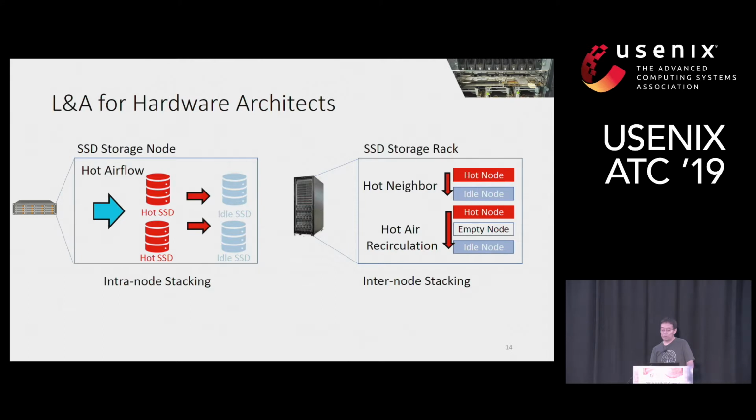In our logs, we have seen SSDs rise above the ambient temperature by up to 25 degrees C or higher. The paper has more details on how, in our experiment, each type of passive heating can heat up an idle SSD under our standard rack setup. The reason this only happens in the one particular data center is that in all the other data centers, a service owns a whole rack. All the nodes in the rack belong to the same service. So they have similar workload and similar temperature, not much interference with each other.